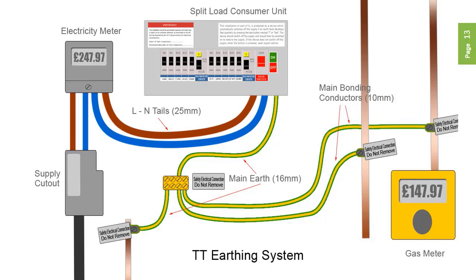The external earth fault loop impedance, or ZE, is high — massive in some cases — and should not exceed 200 ohms. Because of this high value, a TT system will always have additional RCD protection provided.